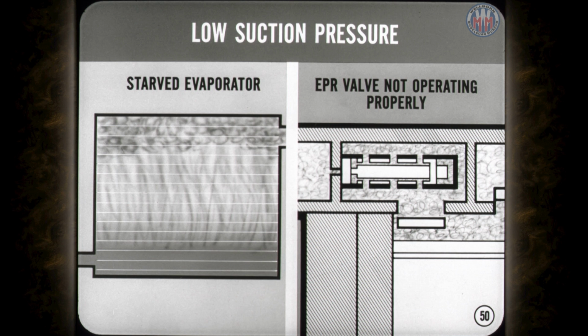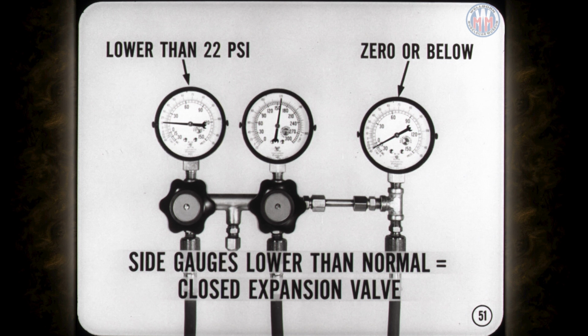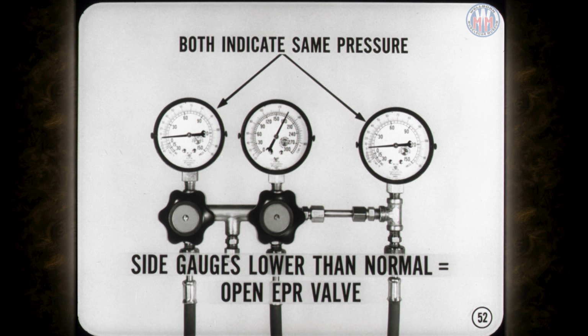A starved evaporator puts out warm air, but an open EPR valve cannot slow down the cooling cycle, so the evaporator will be cold. If suction pressure is lower than the normal 22-pound minimum and inlet pressure drops to the zero line or below, you'll probably find a closed expansion valve. Thank you, Tech. Now, when the EPR valve stays open, both side gauges indicate the same lower than normal pressure, but neither one drops to zero or below as with a closed expansion valve. Keep in mind the fact that suction pressure must stay above 22 pounds.